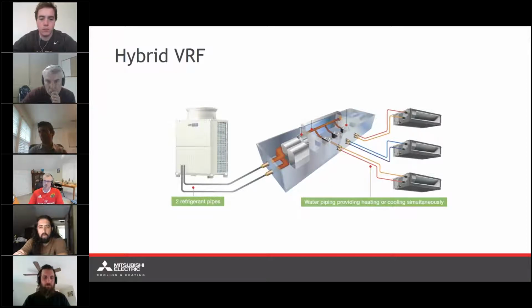So introducing hybrid VRF. What we're looking at here in this schematic, we have the condenser unit outdoors, serving refrigerant piping to the hybrid BC or HBC controller. So we're going to have two pipes of refrigerant piping leading from the outdoor unit to the branch circuit controller, and that's it for refrigerant. In terms of R410A refrigerant, that's all that we're going to be seeing in the system. Everything downstream of the hybrid BC controller is going to be water piping. So when I said that the HEX unit is essentially built into each individual port, obviously it's not a whole HEX unit. Those are a little bit beefy, but it's the components that make up a refrigerant-to-water heat exchanger in each individual port of the HBC controller. So we can provide water piping downstream and provide simultaneous heating and cooling for each fan coil in the system.